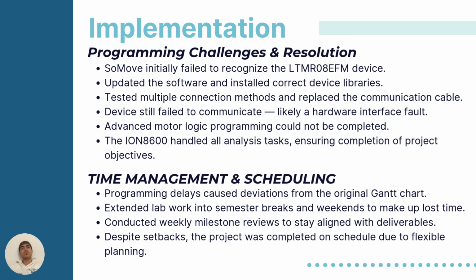Programming challenges and resolution. So we did have this one problem, which is the software. We didn't manage to program because there's a problem in the relay itself, the LTM R08 EFM. At the beginning, the SoMove software didn't have the option to program the relay. So the IT guys fixed this immediately, but after this got fixed, we came in to start the programming, and another problem came in, which is the software doesn't recognize the relay device. And then I tried to buy another cable, but the software still doesn't recognize the device, which is the relay.